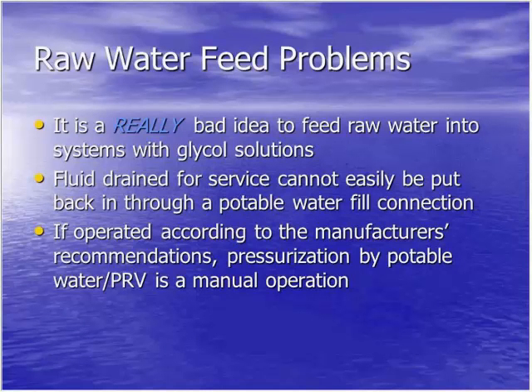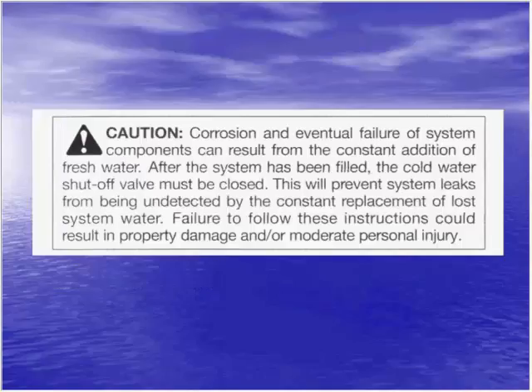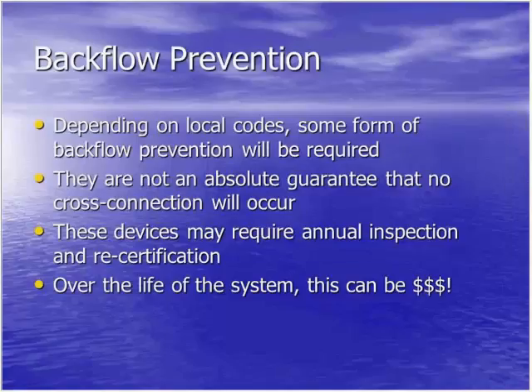This is a label I got off a PRV manufacturer quite some time ago. It states that corrosion and eventual failure of system components can result from the constant addition of fresh water. After the system has been filled, the cold water shutoff valve must be closed. This will prevent leaks from going undetected due to the constant replacement of lost system fluid, system water. Failure to follow these instructions could result in property damage and/or moderate personal injury. So they're just stating there that they want it closed. So if something does happen, you're not going to have your Porsche covered in ice.